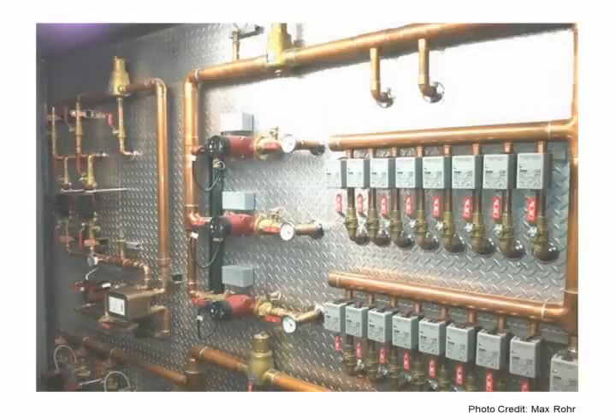Now, when we design a hydronic system, and here's one in front of you, some things stand out. First of all, the effects of air. We have a couple of automatic air separators you can see over here. And so the question is, how do these work? Where do you apply them? Where in the system does the engineer put an automatic air separator? They're meant to operate under pressure and expel air as it builds up. But can they bring in air or suck in air into the system and cause problems?